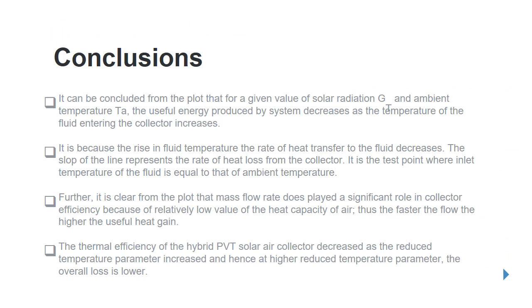In conclusion, it can be concluded from the plot that for a given value of solar radiation and ambient temperature, useful energy produced by the system decreases as the temperature of the fluid entering the collector increases. It is because rising fluid temperature reduces the rate of heat transfer to the fluid.